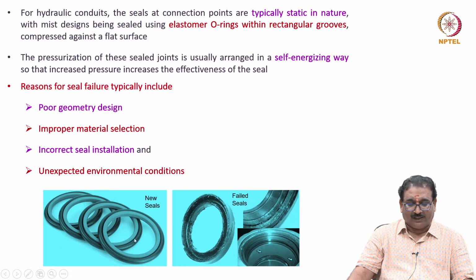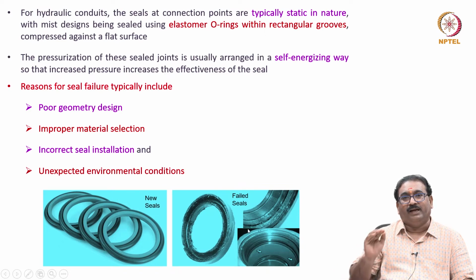These are the new seals, how they will look, you will see, friends, here. These are the failed seals after using in the hydraulic component. You will see how they are worn out inside and also at the side edges, and these are carried in the fluid. Also they will get contaminated.